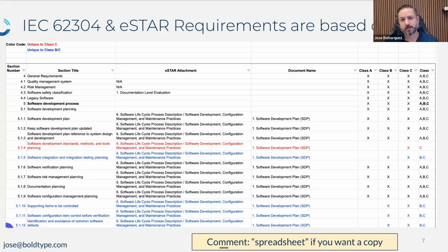Sometimes it's a good practice anyway. There are products that we develop where, as an example, unit testing is not required if you're Class A or even Class B, but it is for Class C, and it is for enhanced documentation for FDA. You have to actually submit the unit testing results, not just provide a summary. So being aware of that early, so that you incorporate unit testing into your system, is really important. You don't want to get to the end of your development process and then realize that FDA is going to ask for all your unit test documentation and you didn't do unit testing. You're not going to get the benefit of it. It's beneficial to do it, and it's going to be a lot more work.